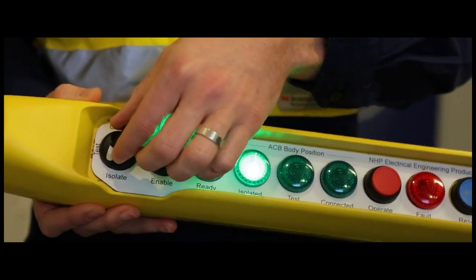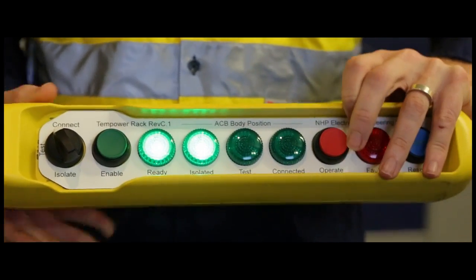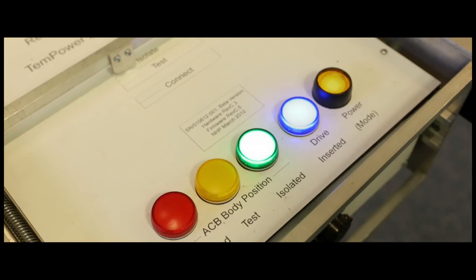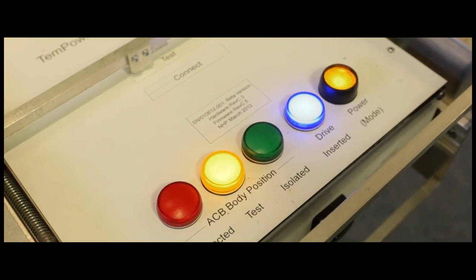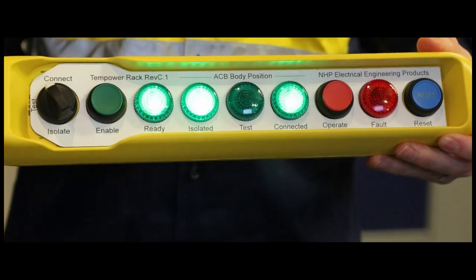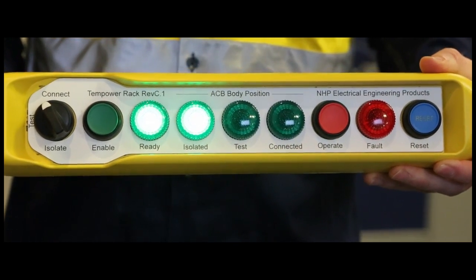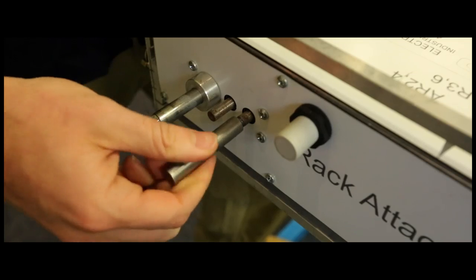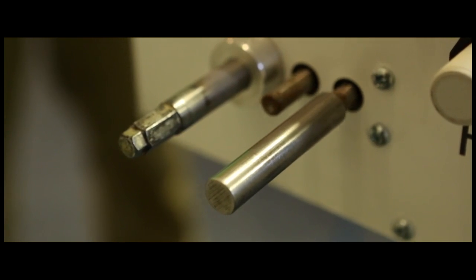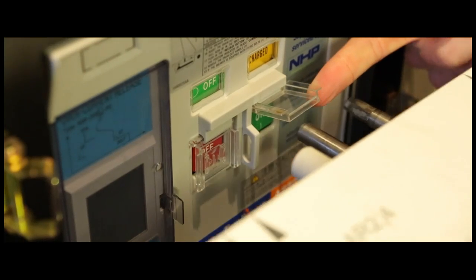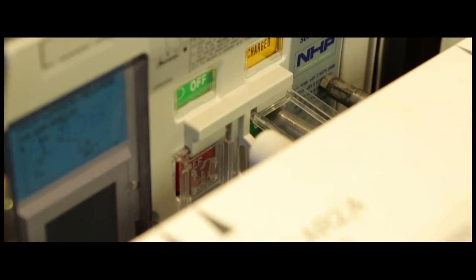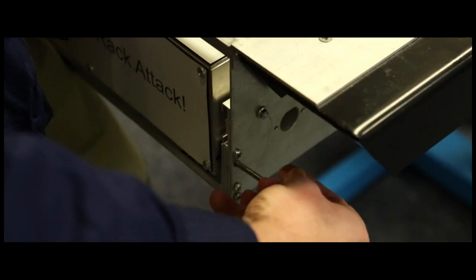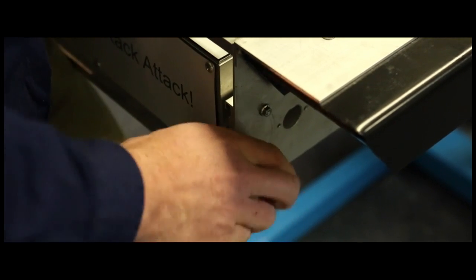The ACB is racked into position by simply selecting the position on the selector switch and pressing the two buttons. The indication lamps on the pendant and the drive will light up to show the current position and flash to show the position that was selected. The TemPower Rack can be used to close the ACB by operating the push buttons. The TemPower Rack comes with two locking pins to hold the drive mechanism in retracted position when not in use.